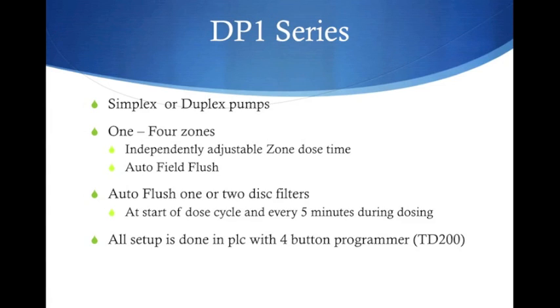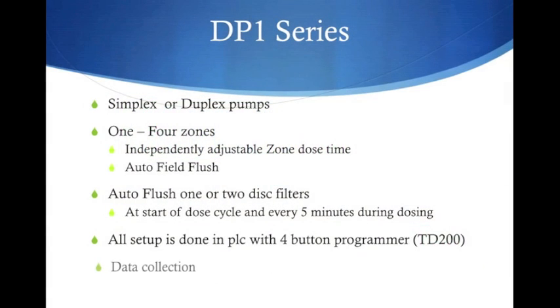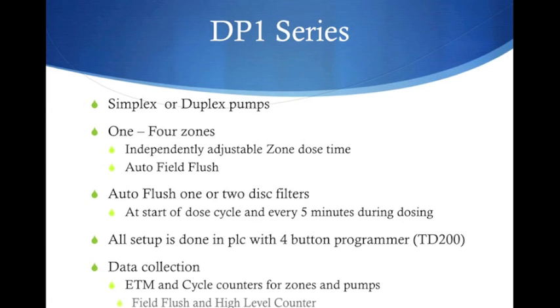All setup of the DP1 series is done in the PLC with a four button programmer. This is the four button TD200 programmer which we'll get into more detail here in a few minutes. The DP1 series also provides data collection through utilization of elapsed time meters and cycle counters for the zones and pumps and field flush and high level counters.